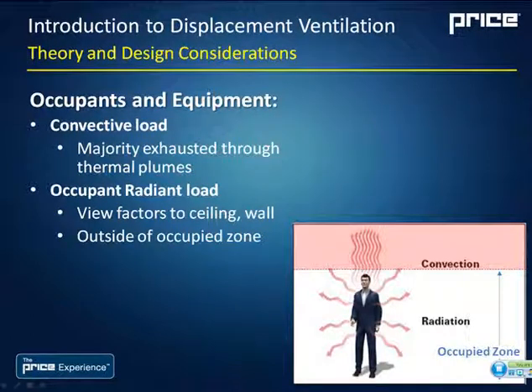So there's three different portions of load that we're concerned with. The first is occupants and equipment. Now, occupants and equipment have a convective load. There's warm air rising off the top of our heads. And the majority of that, again, is going to be exhausted through thermal plumes simply because it's going to rise straight up without significantly mixing or warming the occupied zone.